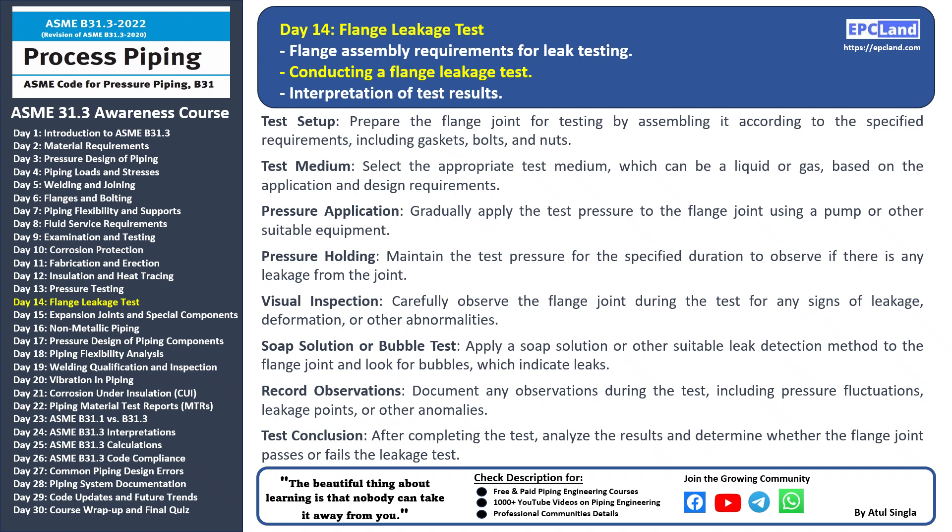Visual inspection: carefully inspect the flange joint for any signs of leakage, deformation, or other irregularities. Soap solution or bubble test: apply a soap solution or use a bubble test method and look for any bubbles forming, as they indicate potential leakage points. Record observations: keep a record of pressure fluctuations, locations of leaks, or any other significant findings. Test conclusion: once the test is complete, analyze the results and determine whether the flange joint passes or fails the leakage test.